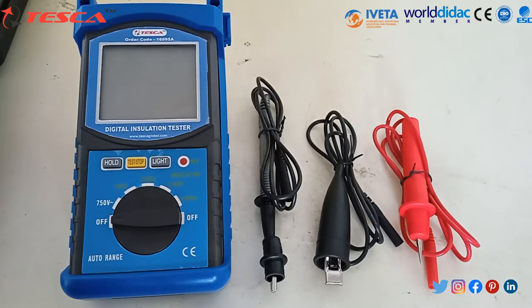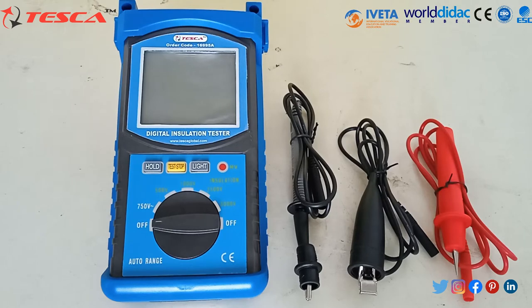The tester can also measure alternating voltage. This tester applies to all kinds of electric equipment and insulation materials such as transformer, electro motor, cable switch, appliance, etc. This meter is designed in accordance with IEC publication 1010, pollution degree 2 and installation category 2. This item should not be used before closing the back lid due to danger of electric shock.